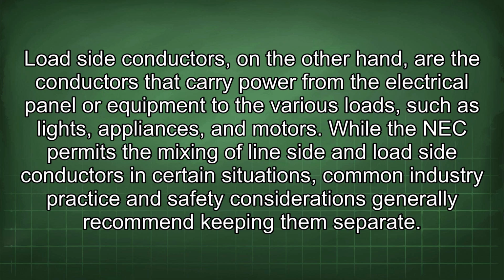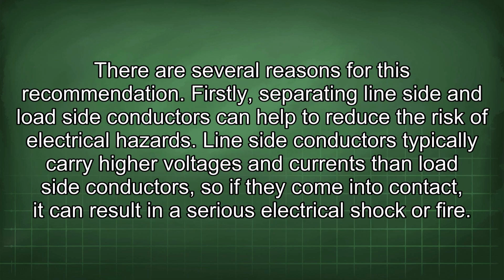While the NEC permits the mixing of line-side and load-side conductors in certain situations, common industry practice and safety considerations generally recommend keeping them separate. There are several reasons for this recommendation. Firstly, separating line-side and load-side conductors can help to reduce the risk of electrical hazards. Line-side conductors typically carry higher voltages and currents than load-side conductors, so if they come into contact, it can result in a serious electrical shock or fire.